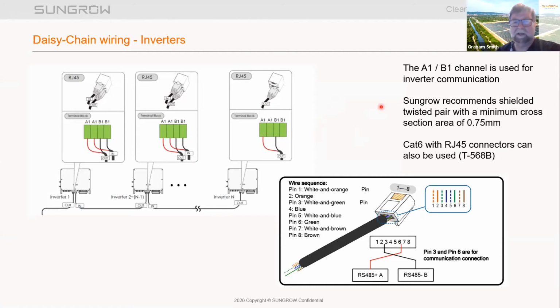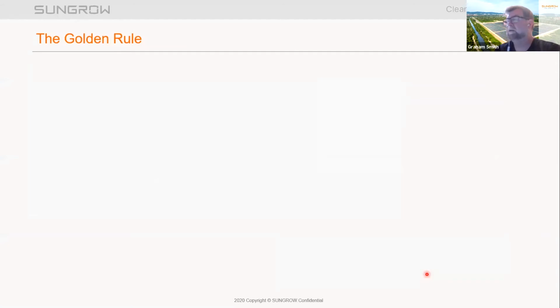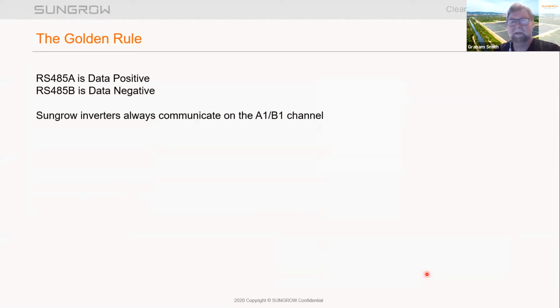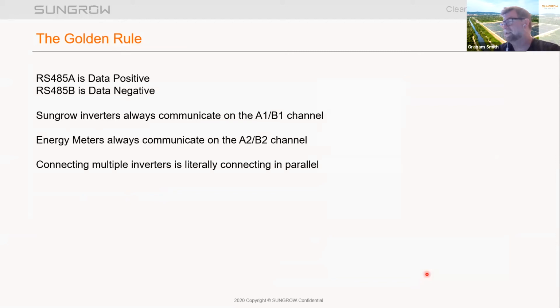Obviously, there's less volt drop across that, you're less likely to lose signal, so we do prefer that you use that. If you are using the RJ45s, pin 6 is the RS485A, and pin 3 is RS485B. Now, the golden rule, and if you keep this in your head, you won't go wrong. This is the basic simple rules to the whole thing, and it'll work. RS485A is data positive. RS485B is data negative. Sungrow inverters always communicate on the A1B1 channel. Energy meters always communicate on the A2B2 channel. Now, if you keep those in your head, you won't get it wrong. Connecting multiple inverters is literally connecting in parallel.